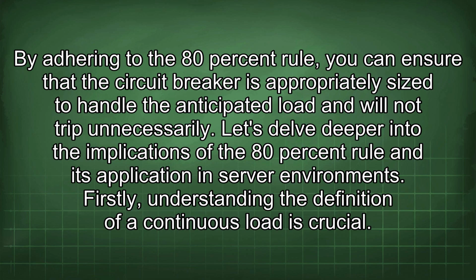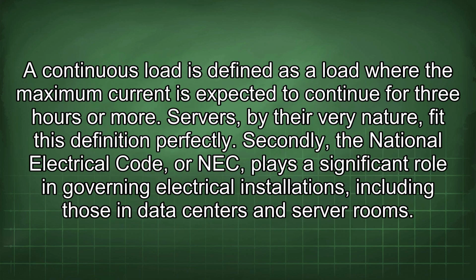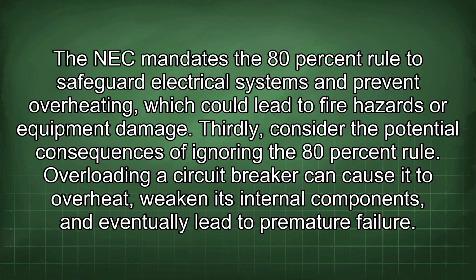Let's delve deeper into the implications of the 80% rule and its application in server environments. Firstly, understanding the definition of a continuous load is crucial. A continuous load is defined as a load where the maximum current is expected to continue for 3 hours or more. Servers, by their very nature, fit this definition perfectly. Secondly, the National Electrical Code, or NEC, plays a significant role in governing electrical installations, including those in data centers and server rooms. The NEC mandates the 80% rule to safeguard electrical systems and prevent overheating, which could lead to fire hazards or equipment damage.